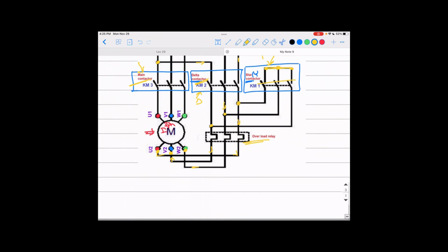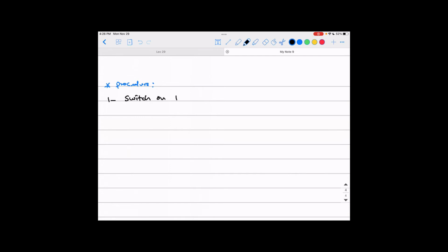So that's basically how you can do this switching from Y connection to delta connection using just those contactors. Okay, so our procedure here. Number one, switch on the main contactor and the Y contactor together to connect the motor as Y.